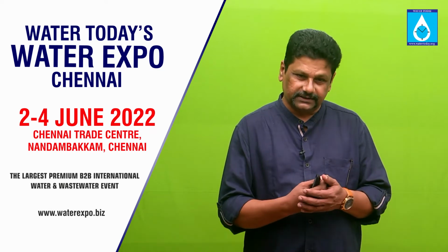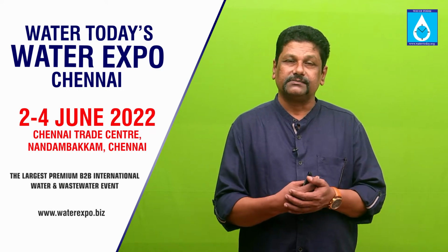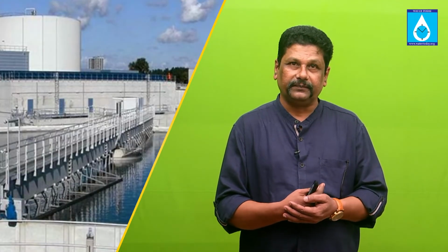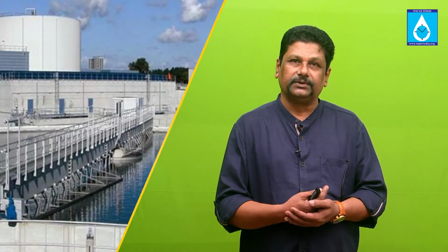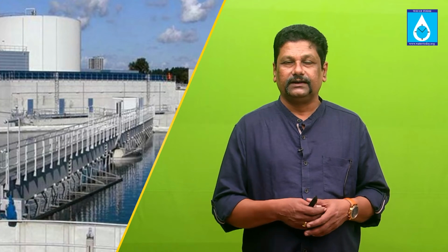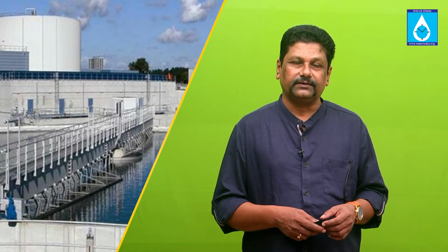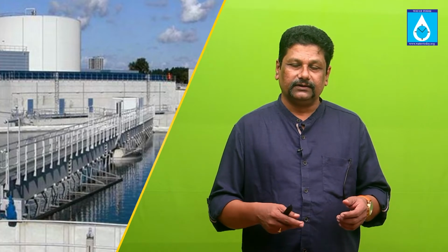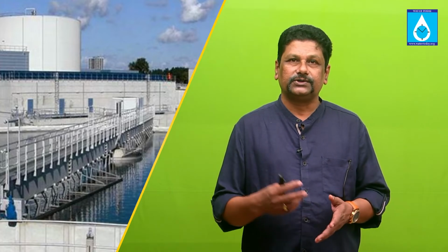Okay, the next question comes: I have some vortex impeller pumps. Yes, you can take a vortex impeller pump, but minimum 65, and 65 also on the commercial side, but not on the municipal side. When you go to the municipal side, it should be above 100 or even 150. The larger the handling capacity of the pump, the better it is for you to handle sewage. So first, drainage, effluent, sewage.